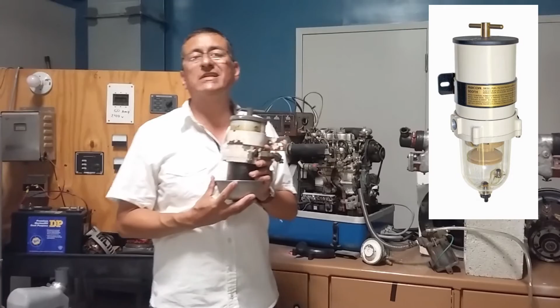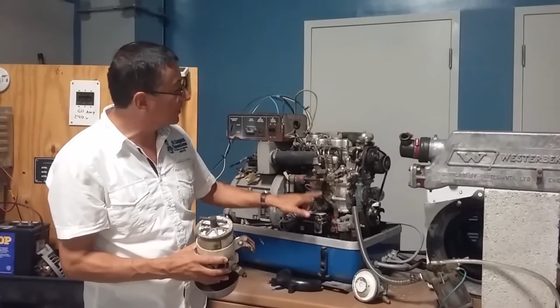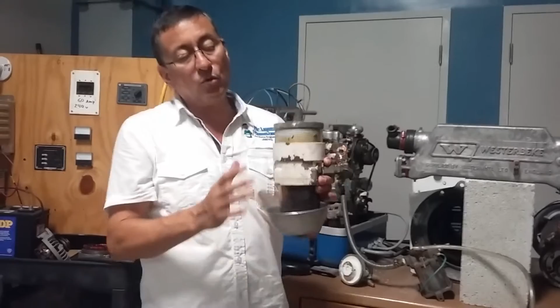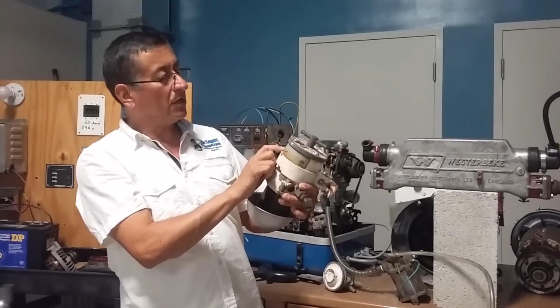Another important element that you need to keep in consideration is the installation of the fuel water separator. The fuel water separator, or primary filter, or water separator filter, should be located after the fuel comes from the fuel tank, and the fuel continues into the secondary filter, and after the secondary filter the fuel enters the fuel injection pump. That fuel filter is located outside of the generator, and that fuel water separator is rated in gallons per hour. Verify the service manual, where you have the manufacturer's recommendation for the water separator filter or primary filter, in gallons per hour.